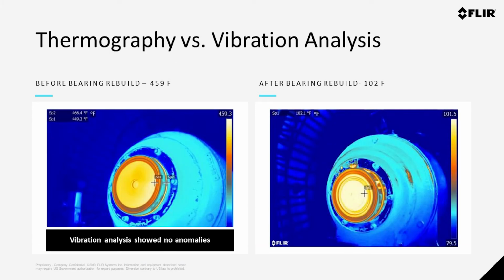One more example of a bearing that was being inspected with vibration analysis as well as thermography. And I'm not making any claims that one technology is superior to any others. The reality is that different technologies are going to give more meaningful results depending on the situation, the application, etc. But in this individual case, vibration analysis was revealing no problems with the bearing. Thermography actually showed it's running hot compared to its historical trend. It led to a rebuild of that bearing under planned outage and minimal disruption, and wound up saving a good bit of time and money for that plant.